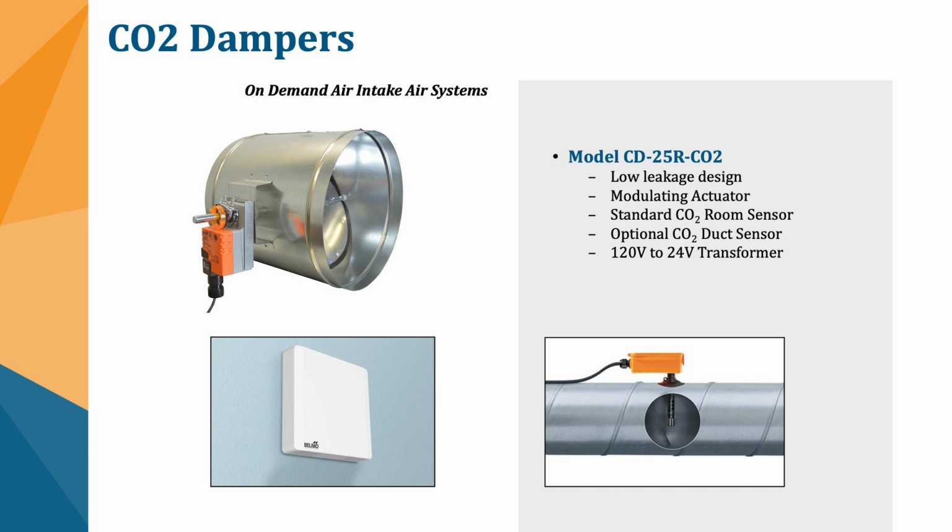Even when you're dealing with a duct sensor, you can certainly measure your CO2 at the damper, at the intake damper, but that typically isn't going to get you what you're looking for as far as a good CO2 reading. The duct CO2 sensors you typically want to install on the return. So you're going to want to measure what air you're recirculating, which is typically going to be a different duct than your intake air duct. So most of the time, like these, they are a bit separate.